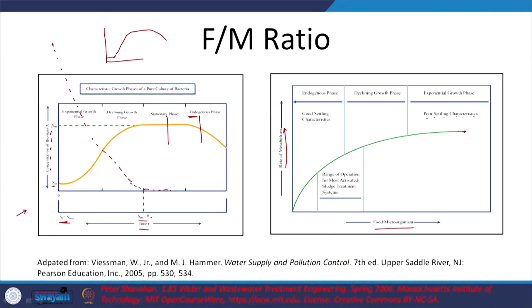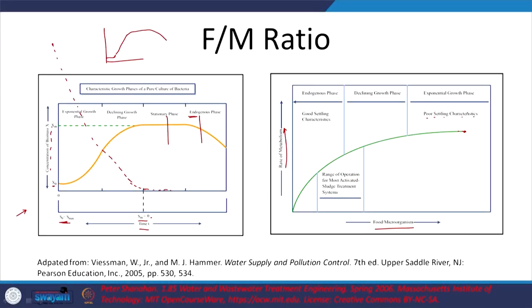Poor settling characteristics result, and with high food in the system, waste is also going to leave through the effluent, so the concentration of waste in the effluent will be relatively higher. If F/M is too low, you get different issues with respect to sludge bulking. We want that sweet spot between the declining growth phase and the endogenous growth phase — that is the ideal range of operation where F/M is not too low but certainly not too high.